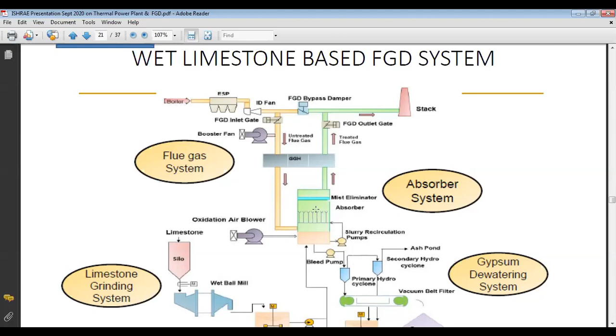The purpose of this oxidation blower is to oxidize the calcium. Basically, the limestone is calcium carbonate, and it reacts with sulfur dioxide to form calcium sulfite. So calcium sulfite is further oxidized to calcium sulfate, which is gypsum, and which is a stable product. So that's why, to enhance the formation of gypsum, this oxidation blower is used. So this is the typical scheme of an FGD system.